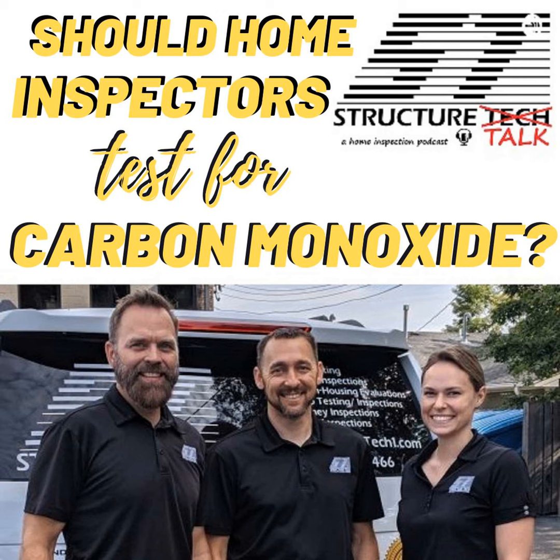I was going to ask you, Reuben, you've taught classes about this before. We've taught classes to real estate agents about this, but I think it's an interesting thing to bring up. What happens when you've got someone who says, well, I've had this furnace tested and certified already, so your high CO reading must be wrong because my furnace is certified? I've run into that before at an inspection where a seller has fought me on that, where I had a number that was above 100 parts per million, recommended it being serviced, and then they came back and said, I just had it certified.